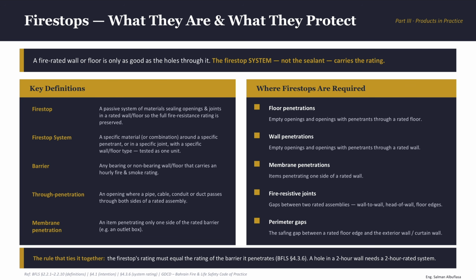Basically, we're trying to protect the protection. I hope that makes sense. And then we have the through penetration and membrane penetration. So basically, the through penetration is where something, a pipe, a cable, a conduit, a duct, passes through both sides of the rated wall. Goes in from one side, goes out from the other side. But the membrane penetration only breaks one side, like an outlet box of electricity. So it penetrates the surface but does not go all the way in.